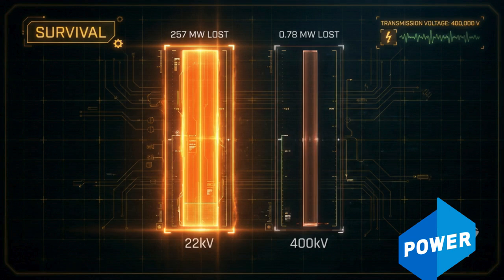Option 2: transmit at 400,000 volts. Current needed is only 1,250 amps. Power lost is roughly 0.78 megawatts. That's not a small improvement. That's going from losing over half your power to losing less than 0.2%. It's not overkill, it's survival.